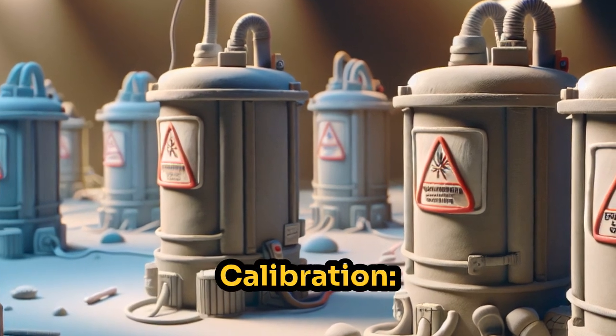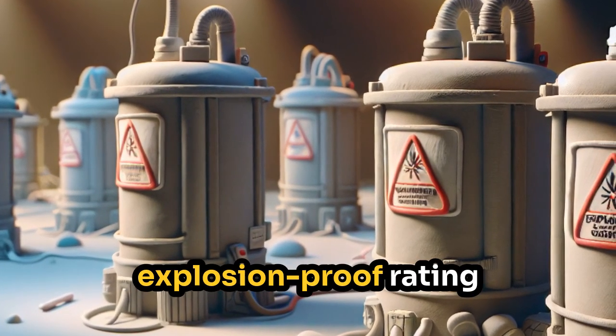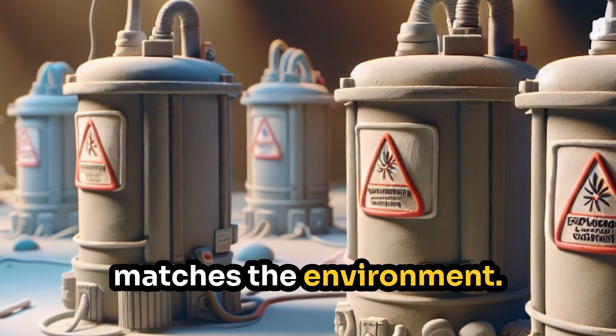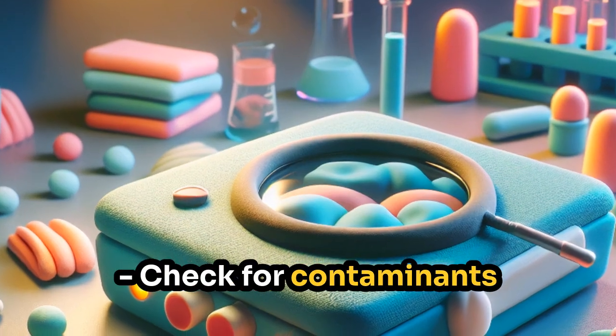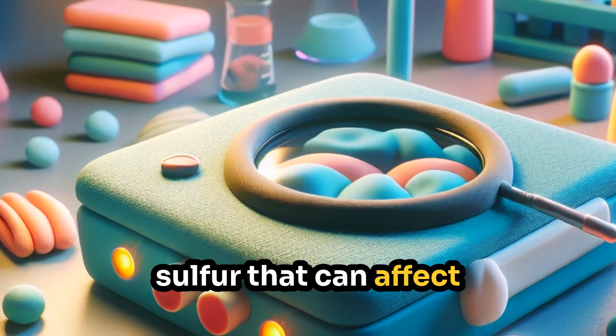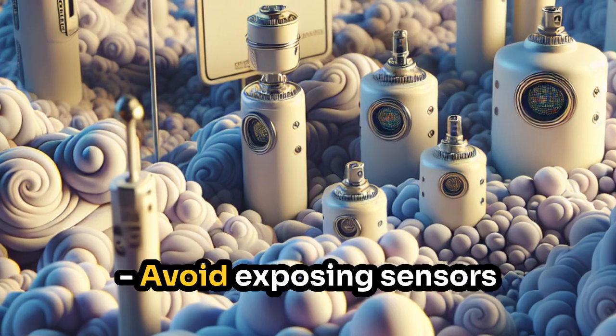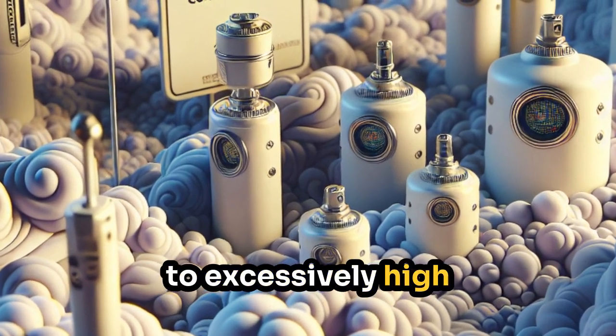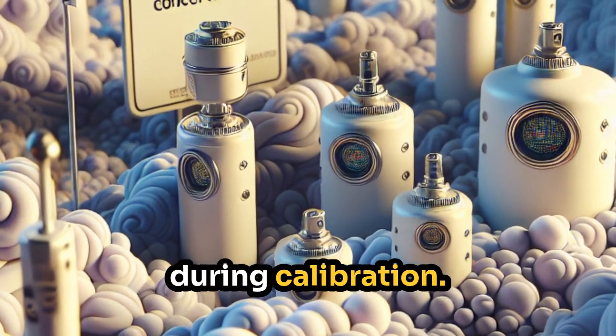Preparation before calibration: ensure the detector's explosion-proof rating matches the environment. Check for contaminants like phosphorus or sulfur that can affect sensor performance. Avoid exposing sensors to excessively high gas concentrations during calibration.